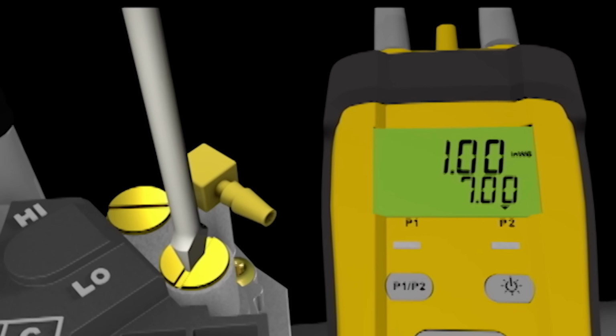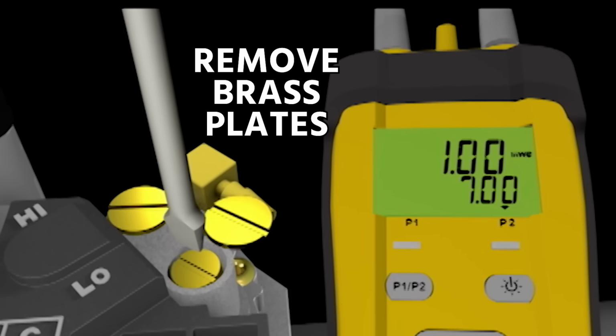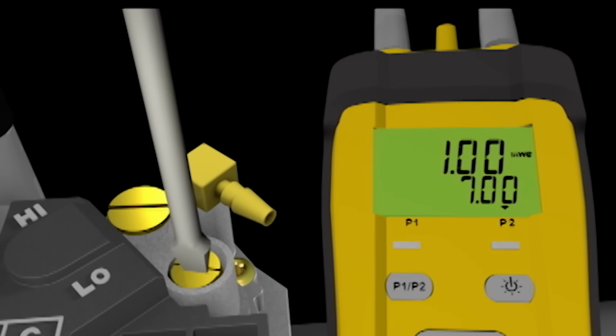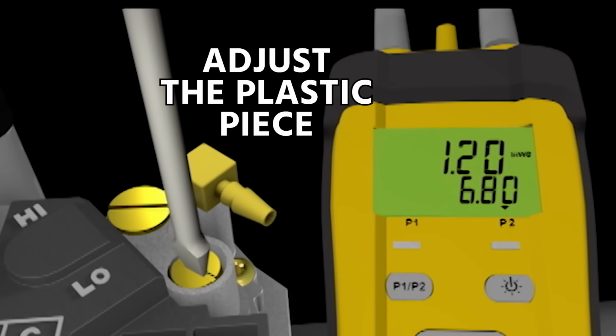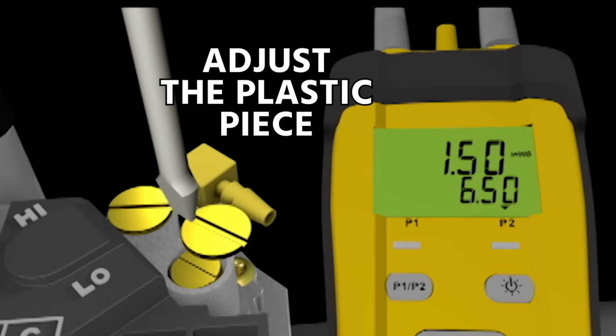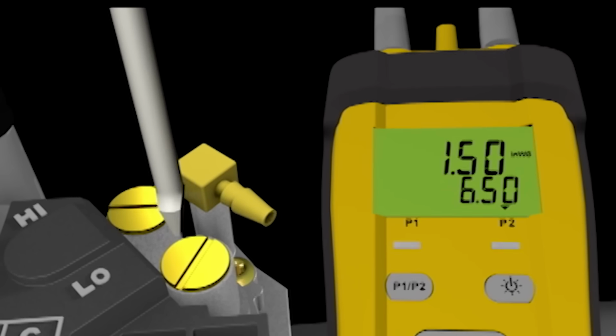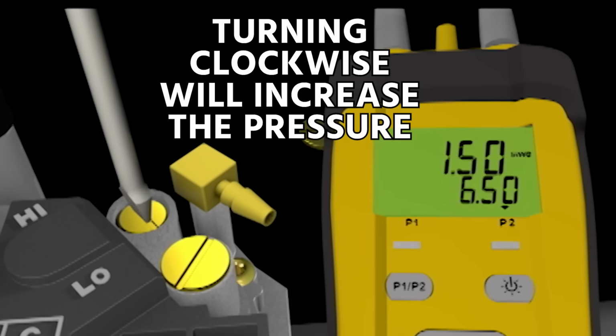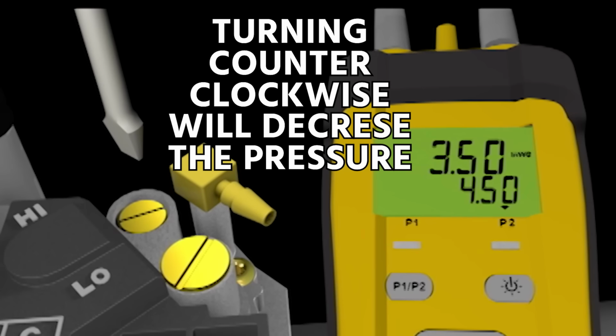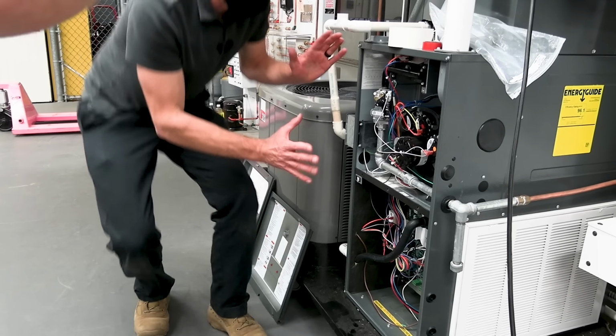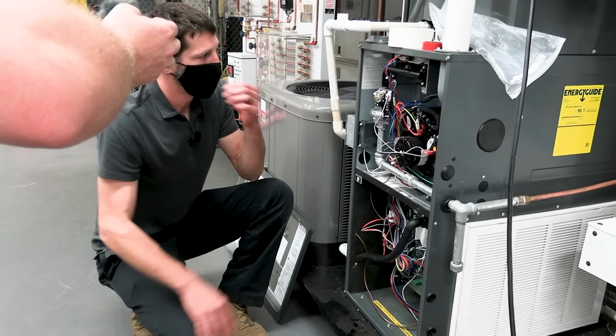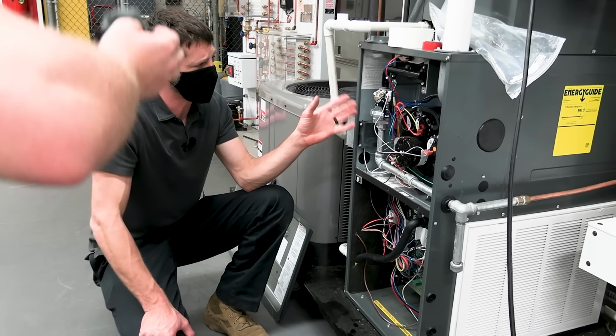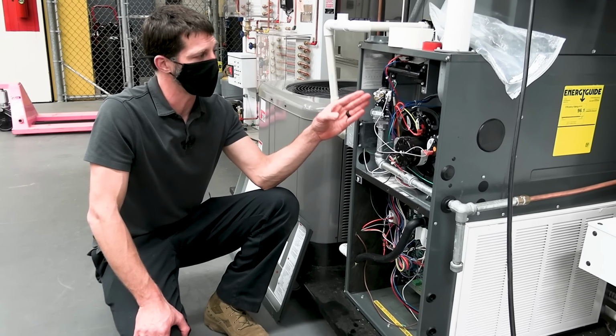But basically, you're going to remove these brass plates right here, and inside there's a little plastic screw, and you're going to be adjusting the plastic piece that's inside of here with a flathead screwdriver. If you turn it clockwise, it's going to increase the pressure. If you turn it counterclockwise, it's going to come out and it's going to decrease the pressure. If you get this set up for natural gas from the get-go, you can do your combustion analysis, but usually it's set up pretty darn close to where it needs to be.